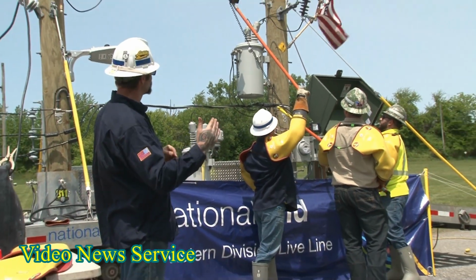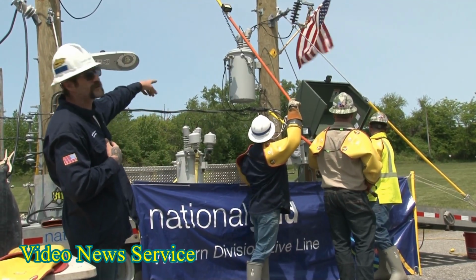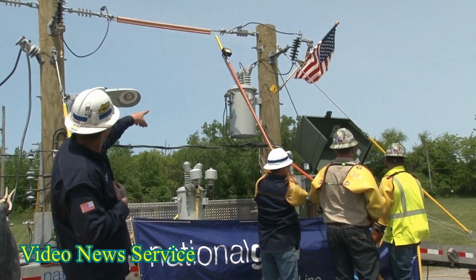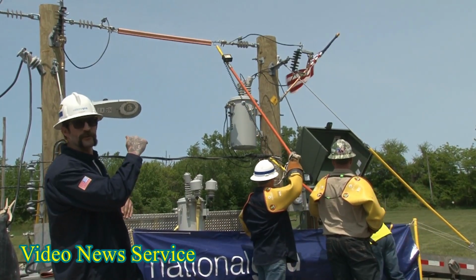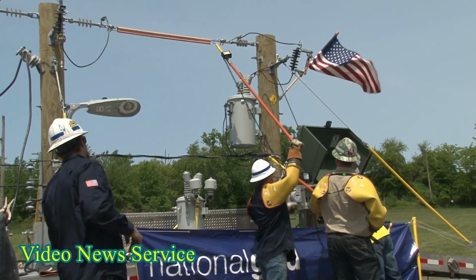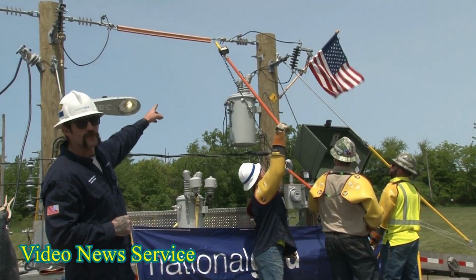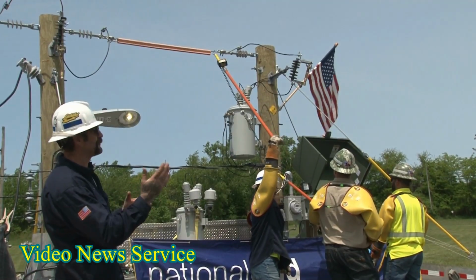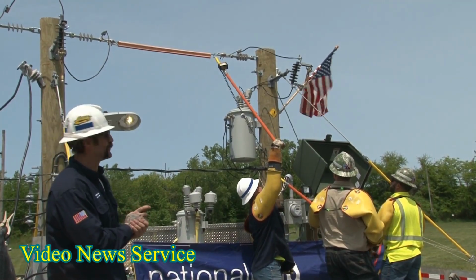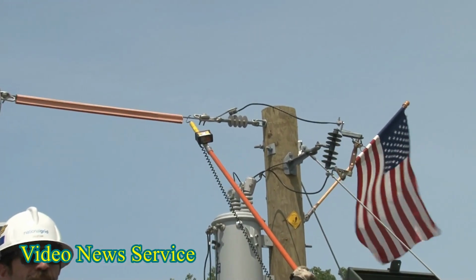From this panel box, like I said, it goes into the meter channel, up out of your weatherhead, up into this transformer. This transformer will actually step that 120, 240 volts up to 4,900. Zoom in, it says 4.9. It's obviously kV, so it's 4,900 volts. This can be very potentially dangerous for us linemen working on these lines.